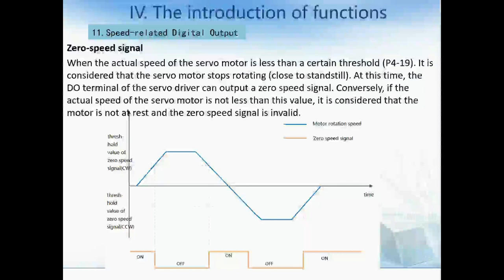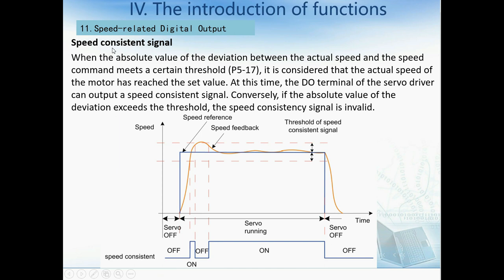The zero speed signal: when the actual speed of the servo motor is less than a certain threshold, the motor is considered stopped. At this time, the digital output terminal of the servo driver outputs a zero speed signal. Conversely, if the actual speed is not less than that threshold, the motor is considered not at rest and the zero speed signal is invalid. Regarding speed consistent signal: when the absolute value of the deviation between actual speed and speed command meets a certain threshold, the actual speed is considered to have reached the commanded value and a speed consistent signal is output. If the deviation exceeds the threshold, the speed consistency signal becomes invalid.